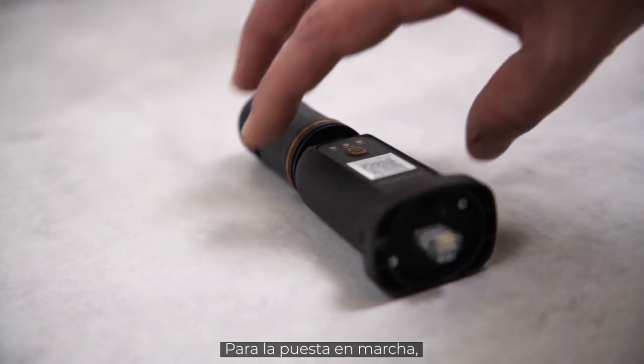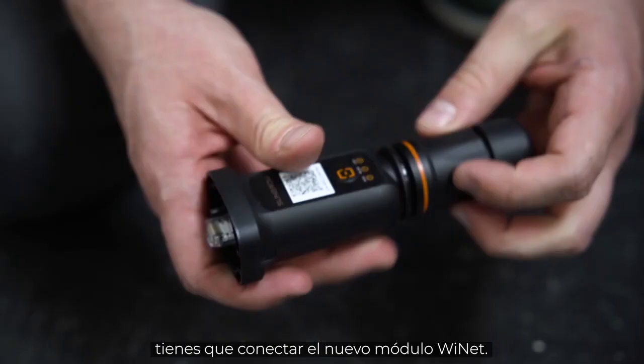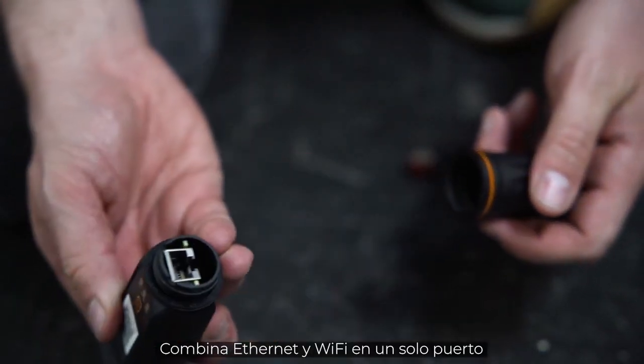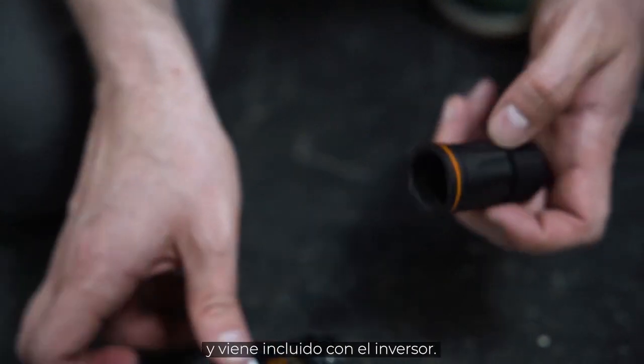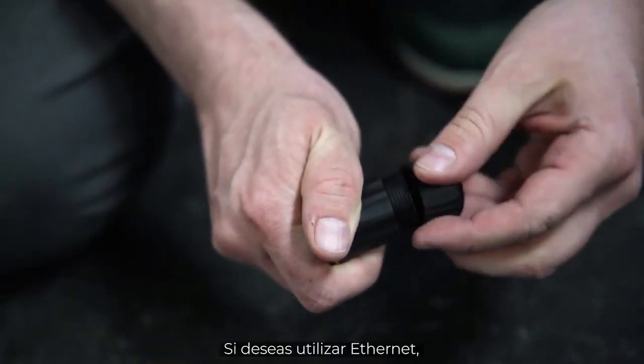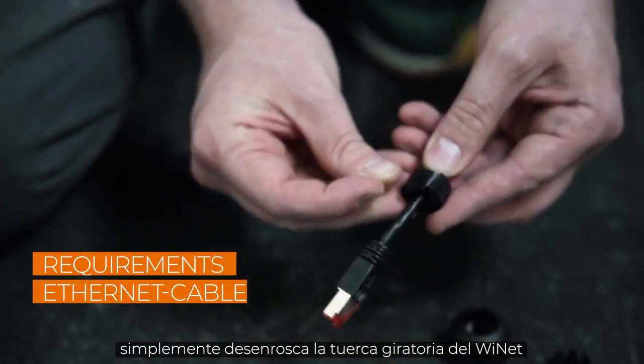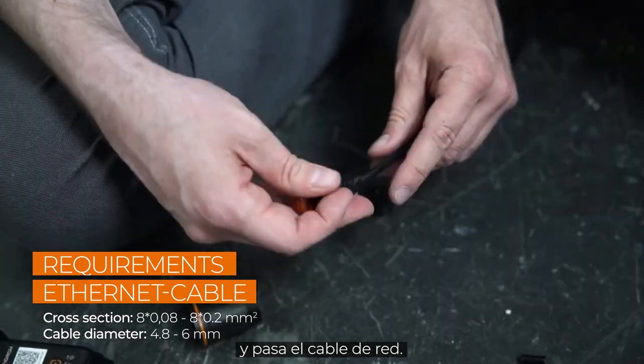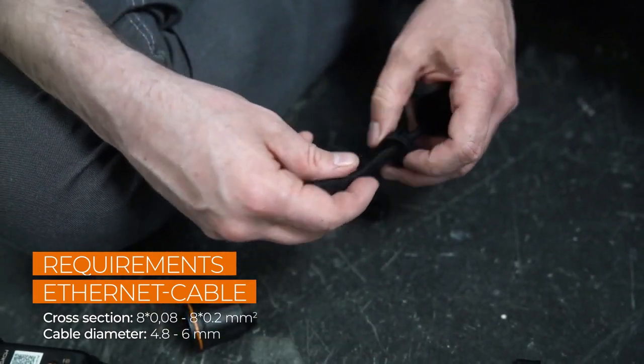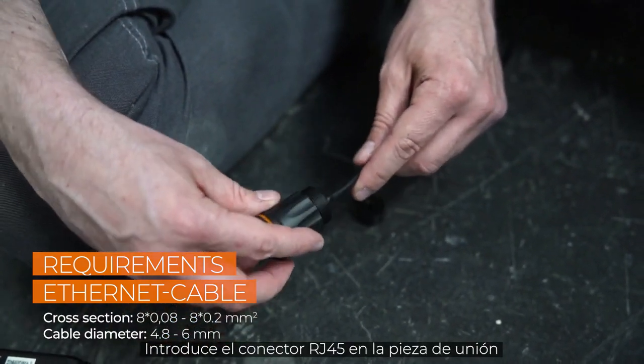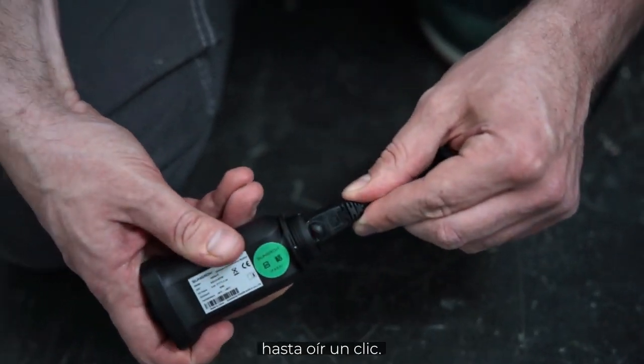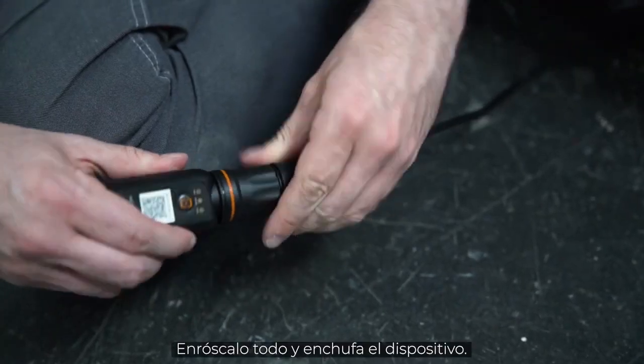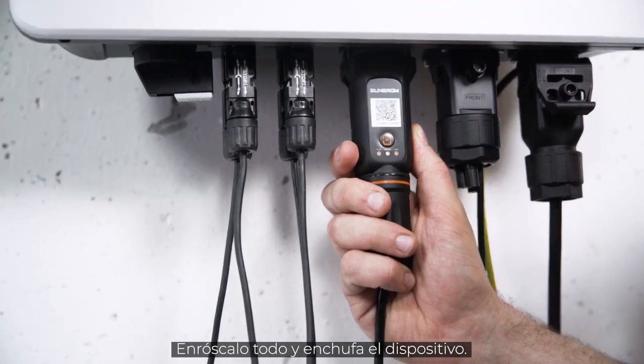For commissioning, you have to connect the new WiNet module. It combines Ethernet and Wi-Fi in one port and is part of the delivery scope. If you want to use Ethernet, simply unscrew the swivel nut from the WiNet S and thread the network cable through it. Insert the RJ45 plug into the plug connector until you hear a click. Screw everything together and plug the device in.